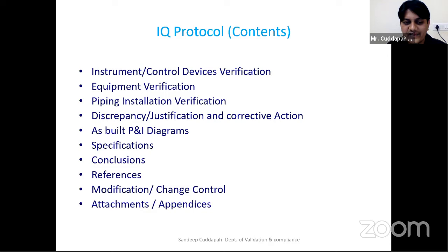And you will have a section called references. In references, if you are doing qualification as per some guideline, you can give the guideline references here, or if you are doing installation qualification based on your factory acceptance test, you will give those factory acceptance references. Then if anything is not meeting, or if anything has to be changed, a change control will be initiated, and based on that change control, you will make modifications in the equipment if necessary. Finally, you will attach all these documents to this installation qualification.